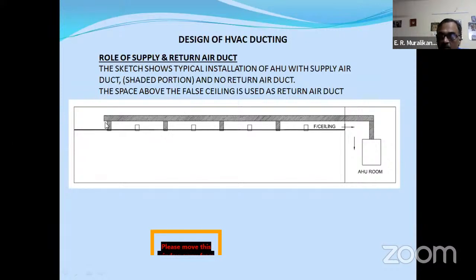Now, what will happen here? This air, since it is not considered in the heat load, will also have some stored heat, or will be picking up heat from different sources above the false ceiling. So all this heat will travel to the AHU coil only. So instead of a 20 TR coil, you may require a 22 TR or 24 TR coil. And you mostly face this problem in summers, because in summer this effect will be felt very high compared to normal seasons.